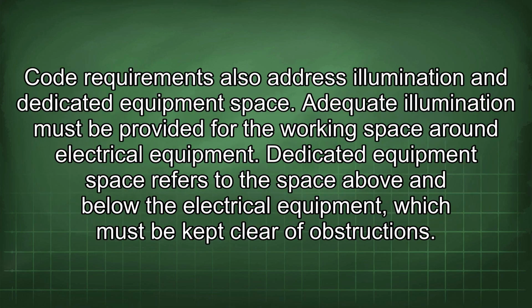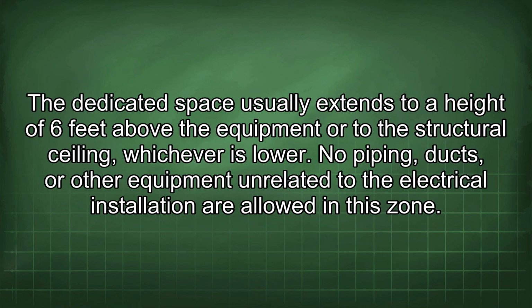Code requirements also address illumination and dedicated equipment space. Adequate illumination must be provided for the working space around electrical equipment. Dedicated equipment space refers to the space above and below the electrical equipment, which must be kept clear of obstructions. The dedicated space usually extends to a height of 6 feet above the equipment or to the structural ceiling, whichever is lower. No piping, ducts, or other equipment unrelated to the electrical installation are allowed in this zone.